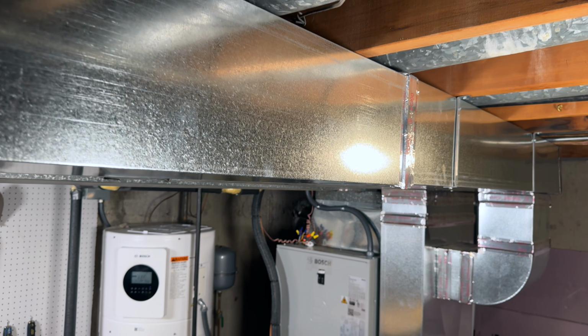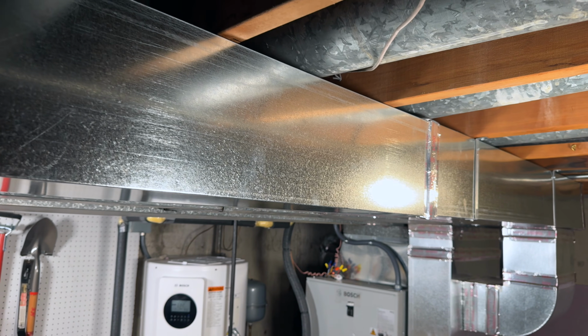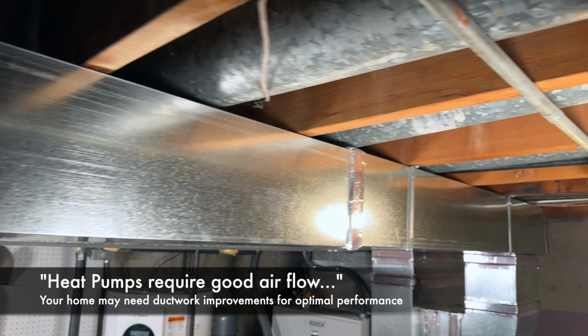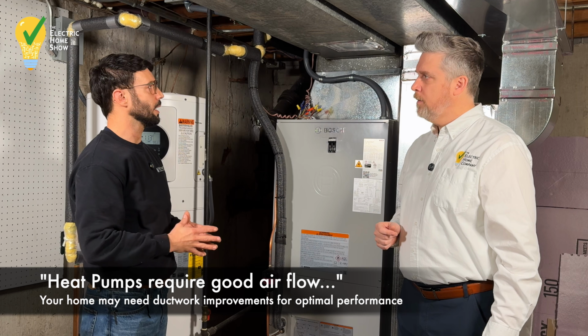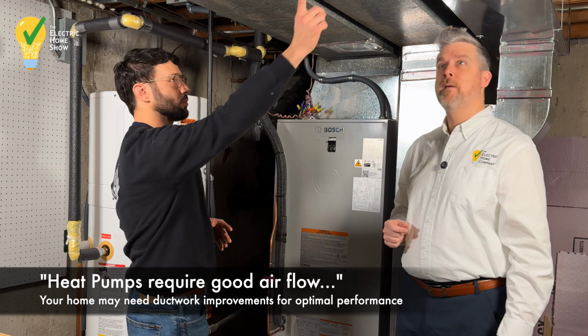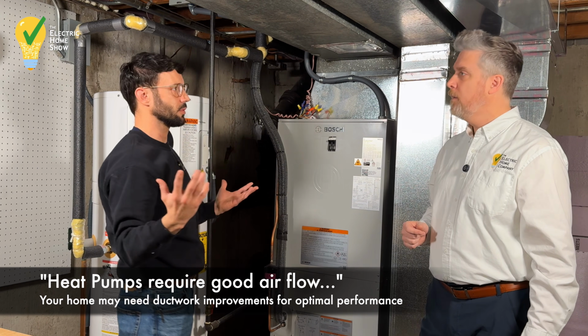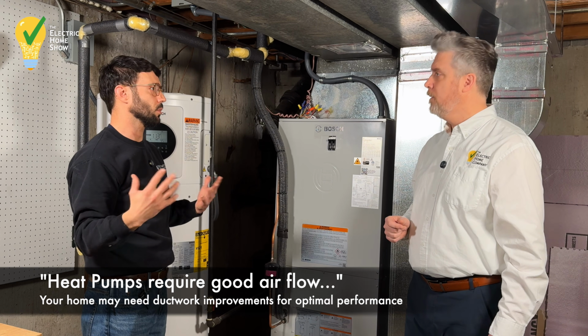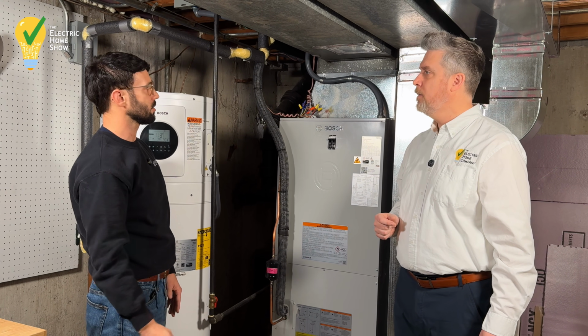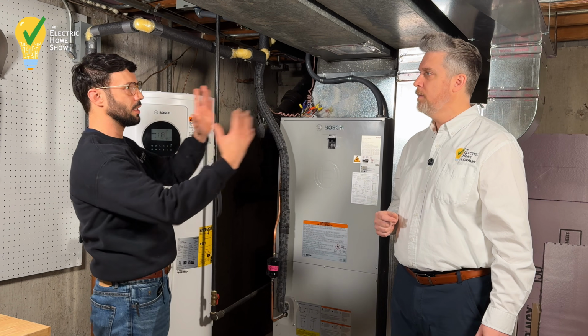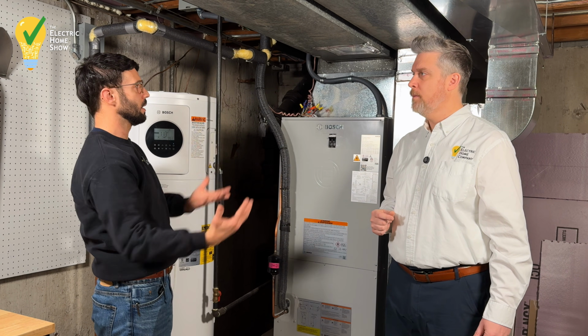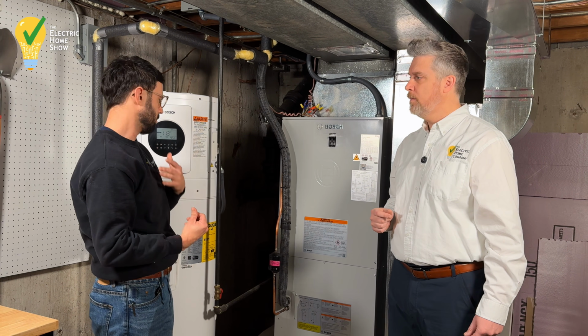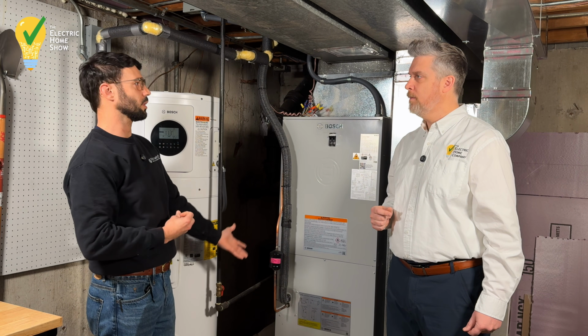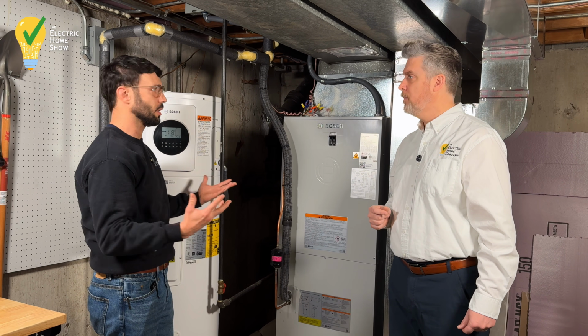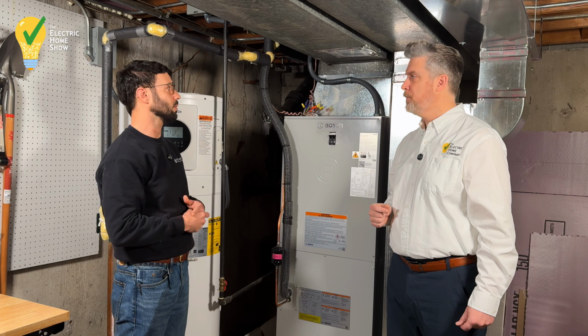What makes the ductwork special when doing a heat pump system? Heat pumps require good airflow. The first thing we noticed was that this return was sized for 1 ton of air conditioning. So with an undersized return, we had to double it to give them the efficiency and to make sure we weren't putting too much torque on the motor, for the longevity of the system. That was important.